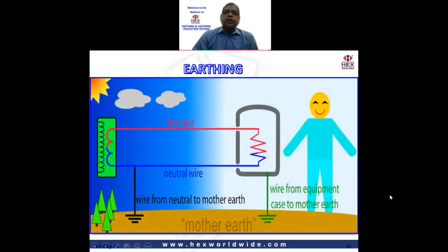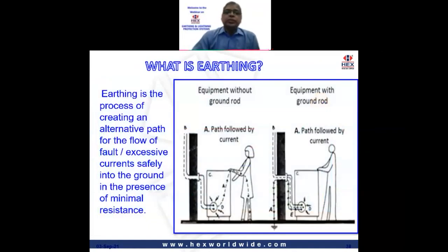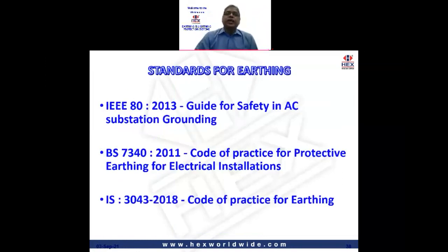Moving on to lightning protection, let us take a look at earthing. I'm sure you all know the simple definition of earthing: it is just a process of creating an alternative path for the flow of fault or excessive current safely into the ground in the presence of minimal resistance. These are the standards that we follow for designing our earthing system: IEEE 80:2013, BS 7430-2011 and IS 3043-2018. All the calculations are done as per the formulas given in these standards.